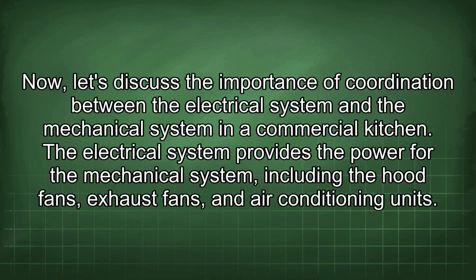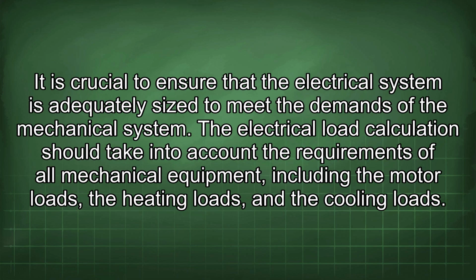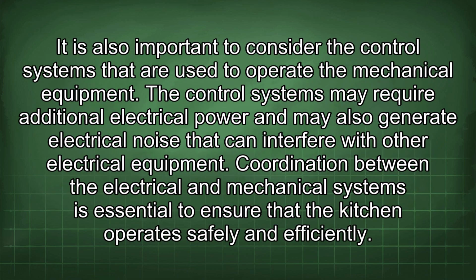Now, let's discuss the importance of coordination between the electrical system and the mechanical system in a commercial kitchen. The electrical system provides the power for the mechanical system, including the hood fans, exhaust fans, and air conditioning units. It is crucial to ensure that the electrical system is adequately sized to meet the demands of the mechanical system. The electrical load calculation should take into account the requirements of all mechanical equipment, including the motor loads, the heating loads, and the cooling loads. It is also important to consider the control systems that are used to operate the mechanical equipment. The control systems may require additional electrical power and may also generate electrical noise that can interfere with other electrical equipment. Coordination between the electrical and mechanical systems is essential to ensure that the kitchen operates safely and efficiently.